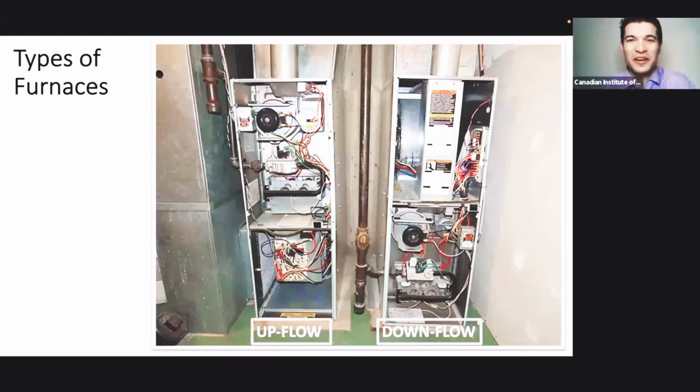Yeah, very common. Absolutely. And some older furnaces will have hidden compartments. I've definitely come across furnaces that have never had their filter changed in 50 years because they didn't know it was installed in the back of the unit, like a low-boy typically.